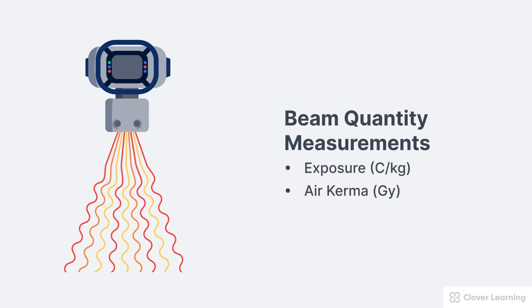When discussing x-ray beam quantity or intensity, we use specific measurements. Quantity is measured as exposure in units of coulombs per kilogram, or we can measure the quantity — that's the intensity — as air kerma in units of gray. These measurements basically tell us how much radiation there is in air.